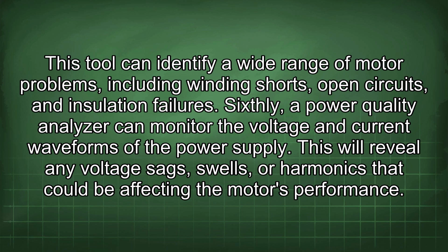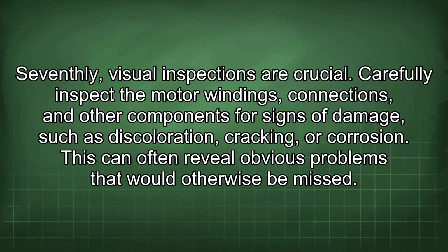Sixthly, a power quality analyzer can monitor the voltage and current waveforms of the power supply. This will reveal any voltage sags, swells, or harmonics that could be affecting the motor's performance. Seventhly, visual inspections are crucial. Carefully inspect the motor windings, connections, and other components for signs of damage, such as discoloration, cracking, or corrosion. This can often reveal obvious problems that would otherwise be missed.